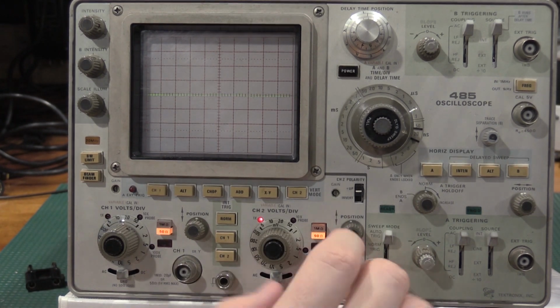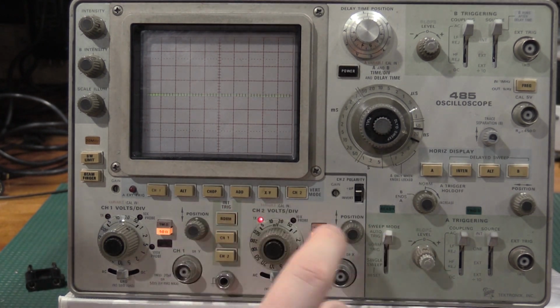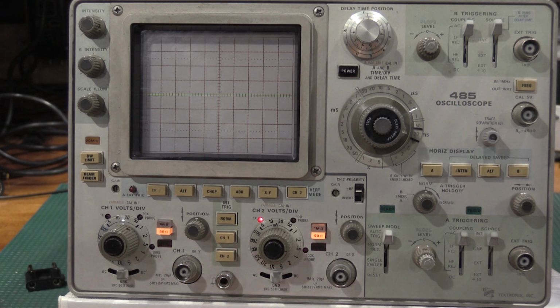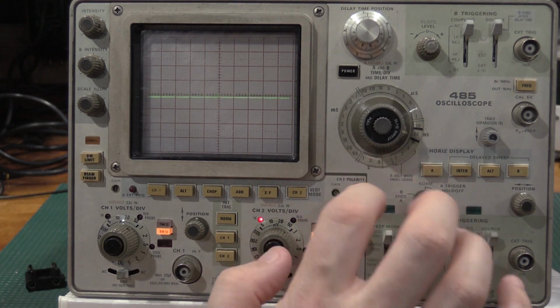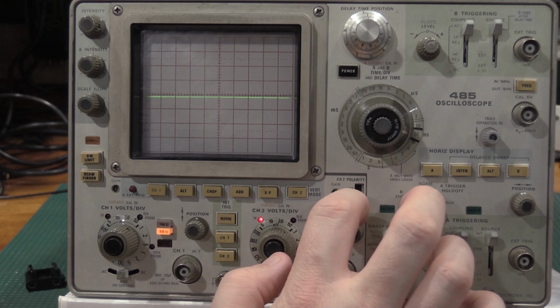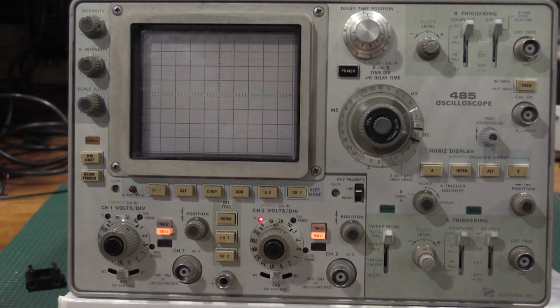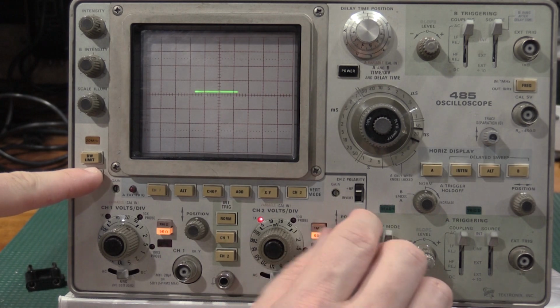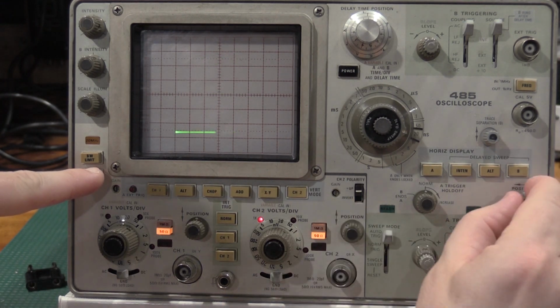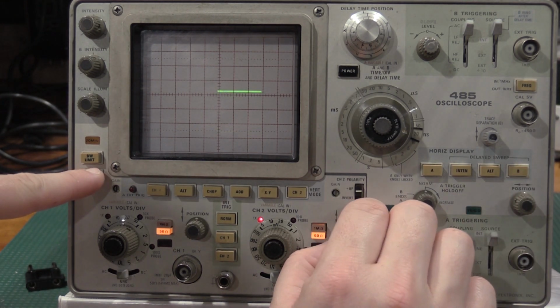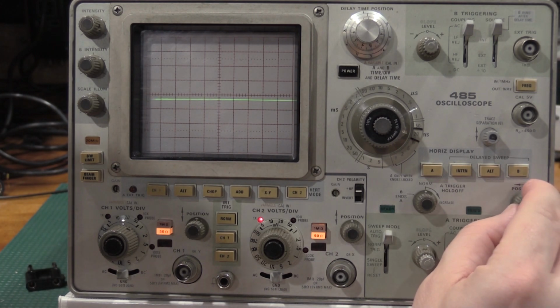Okay, checking the invert shift. 5 millivolts per division, 50 ohms, grounding. And then it shouldn't be more than 0.1 divisions, so we make it just barely, which is fine. And then beam finder. Hit the beam finder, and we can move it. Cannot move it outside the area, so that is working as expected.